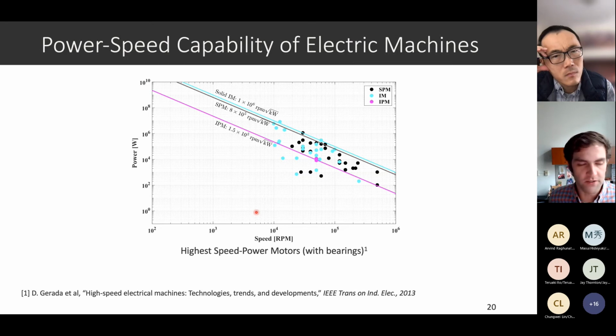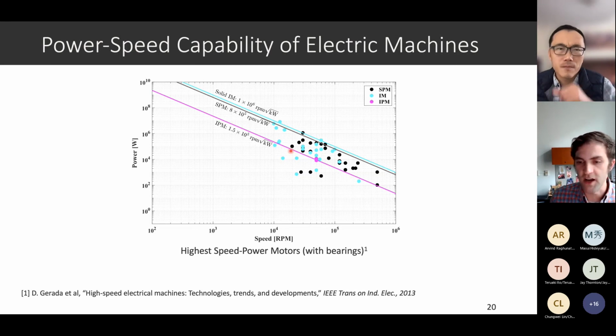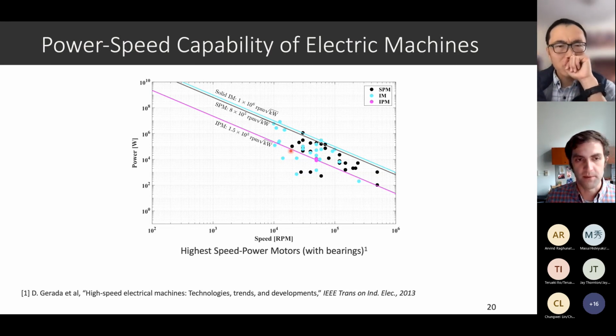So if you're trying to scale the power of your motor, you basically have two fundamental handles: the radius of your rotor, and the length of your rotor. Want to double the power of your motor? Easy, just double the length of the rotor. Except that if that causes a critical speed to come down within your operating speed range, you've got a problem.